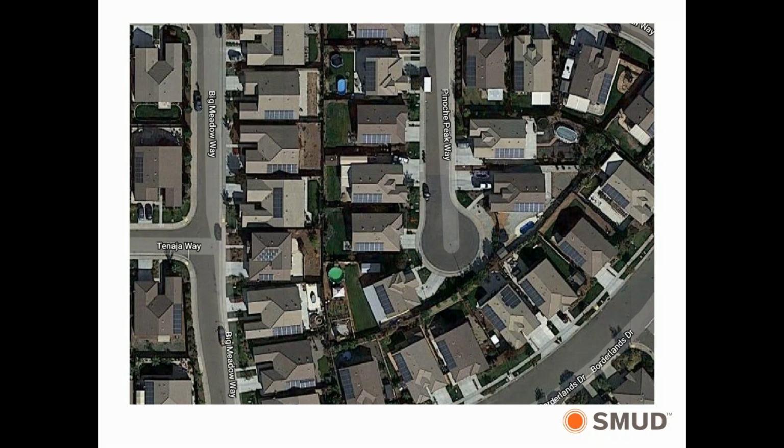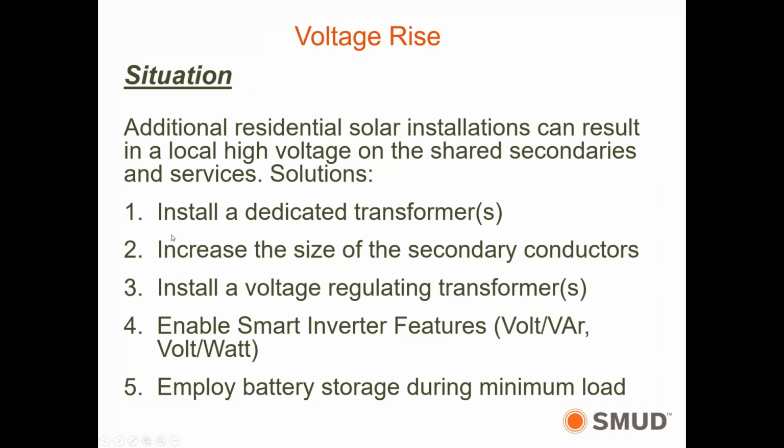So when we do encounter these higher voltages and start dealing with them, that's when things kind of get fun. We've identified a handful of things that we can do to deal with voltage rise. With many of our customers, it doesn't occur very often, but when it does occur, we've used dedicated transformers. We also already require dedicated transformers in residential when the customer has sized their unit over 20 kW. So that takes care of the issue that they might raise the voltage on their neighbors.